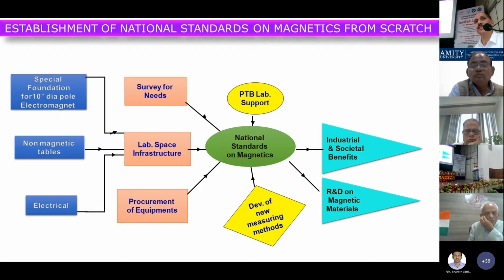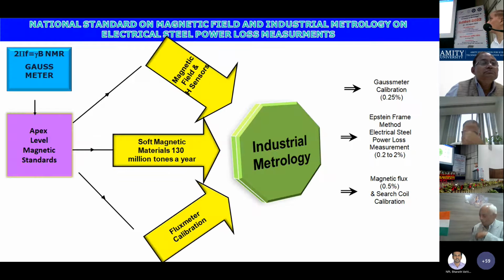We would be doing only the measurements that have been done by others. So we have to look at what our industries need, and if some R&D labs also need some standardization, new measuring methods have to be developed. Here one can see the primary standards, then magnetic field sensors, meaning Hall sensors, and soft magnetic materials, because we produce millions of tons for export as well as for our own use. Then flux meter calibration, and ultimately industrial metrology, where Gauss meter calibration is given with a percentage accuracy.